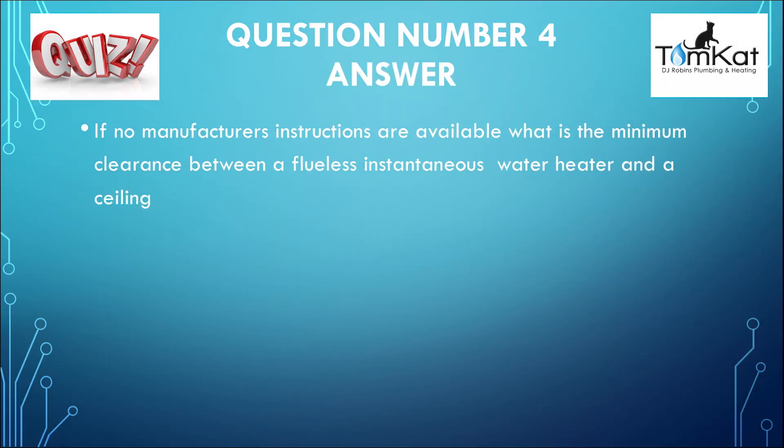Let's look at the answer for question number four: if no manufacturer's instructions are available, what is the minimum clearance between a flueless instantaneous water heater and a ceiling? The answer is C — 300 millimetres. That's the answer for question number four.